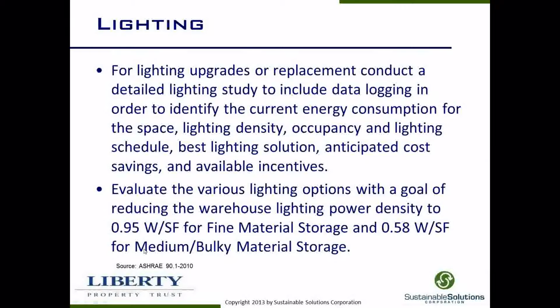We typically look at maintaining lighting power densities at certain levels. For high bay warehouses, we typically look at 0.58 watts per square foot. For activities that require, say, assembly of equipment, or an operation that's fulfilling orders where you're picking things off shelves and doing packaging, it's important to have better lighting. We'll typically look at a target of 0.95 watts per square foot.